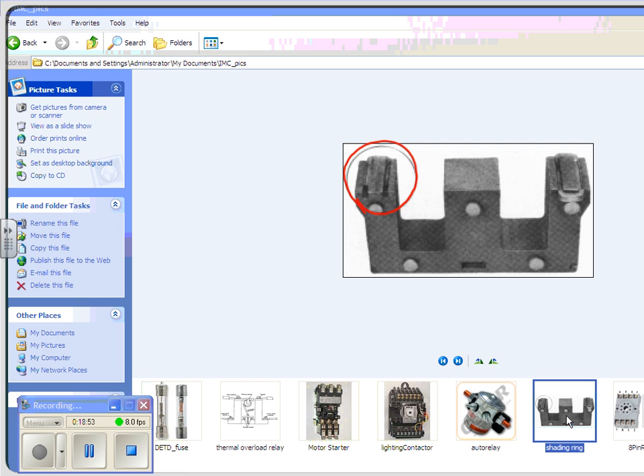You notice this particular one has a shading ring or shading coil on both sides. And that's a very important thing. In the lab, we're going to take a motor starter apart. You're going to have to pull apart the plunger and the coil and look at the 2 parts of the coil. There are 2 parts. And one of them will have a shading coil or 2. And you'll need to identify that.